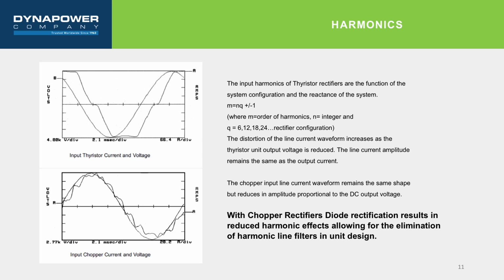As shown in the two diagrams, the input harmonics of the thyristor rectifiers are a function of the system configuration and the reactance of the system. The distortion of the line current waveform increases as the thyristor unit output voltage is reduced, while current amplitude remains the same as the output current. However, the chopper input line current waveform remains the same shape, but reduces in amplitude proportional to the DC output voltage.